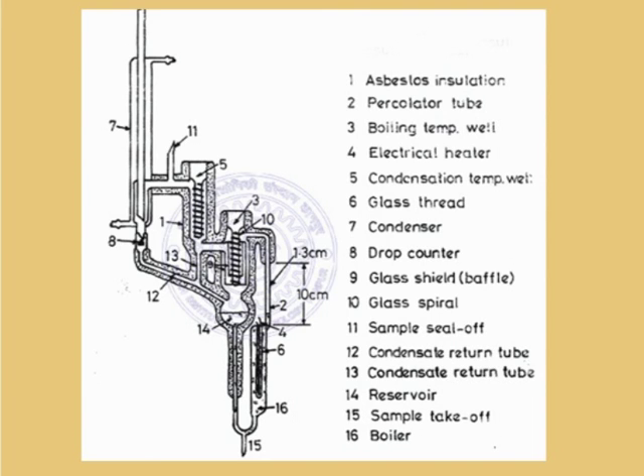This is a sketch of the ebulometer — specifically the differential ebulometer. If you remove one stage, it becomes a simple ebulometer. In a two-stage ebulometer, one stage measures the boiling point and the other measures the condensation temperature. In a single-stage ebulometer, only one stage is present and vapor disengaged from it goes directly to the condenser; condensed liquid comes back and mixes. If a sample is to be taken, it is taken from a separate sampling port — sometimes with a rubber septum so you can use a syringe to draw a sample without disturbing the system.